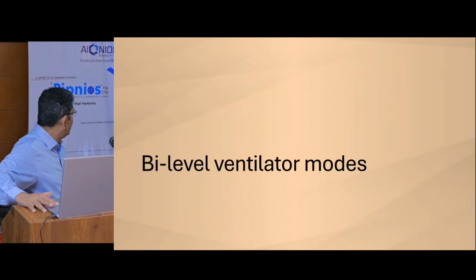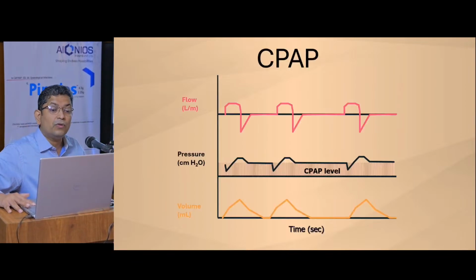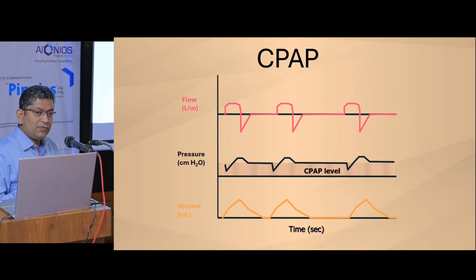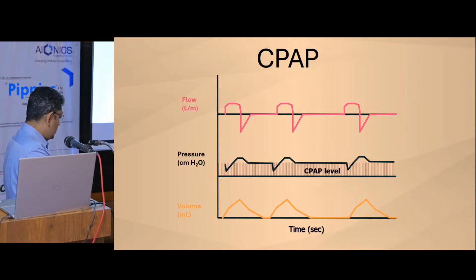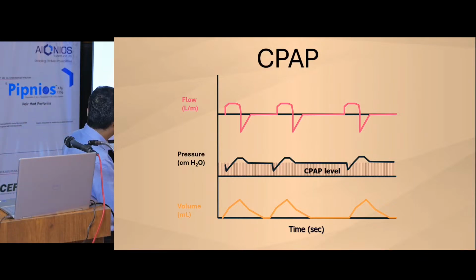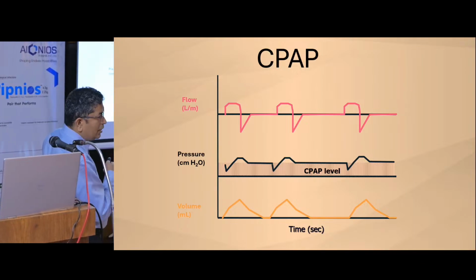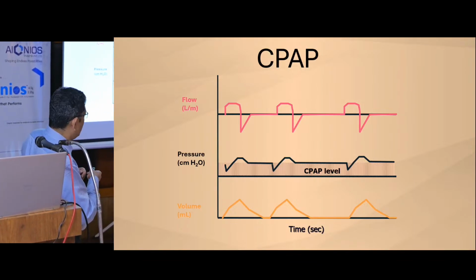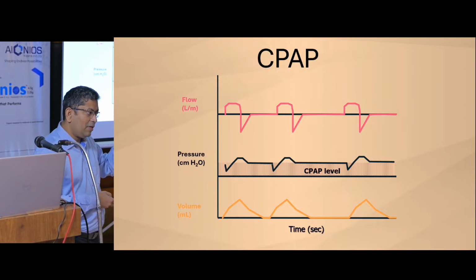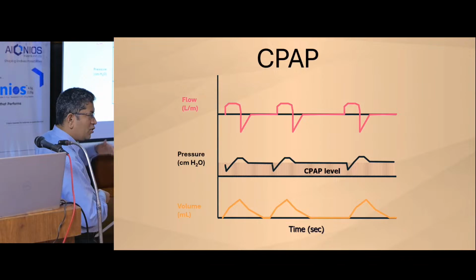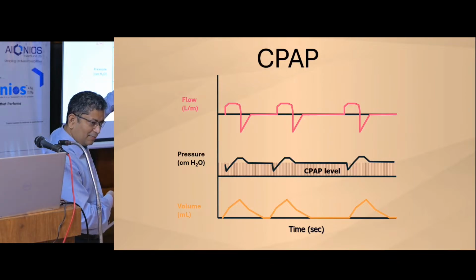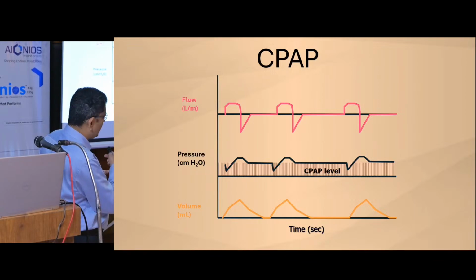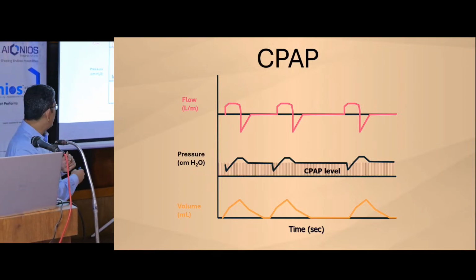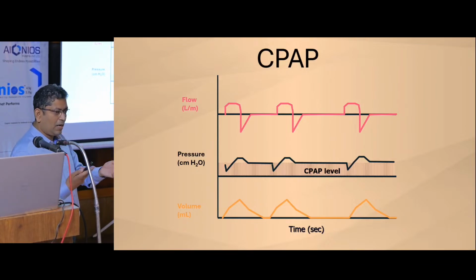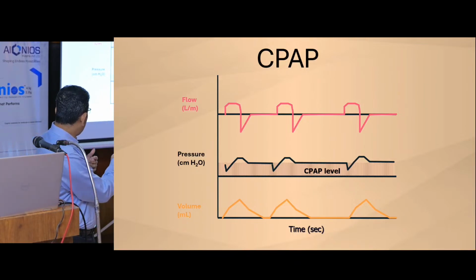And last, not the least, the bi-level ventilator mode. For that, you need to know CPAP. I think everybody knows CPAP. It just gives a pressure support, and the patient can breathe on their own on top of it. So that's the pressure level, and the patient breathes. On inspiration, the flow goes up and the pressure actually comes down here. Normally, in every ventilator, when the patient inspires, the pressure goes up. That's positive pressure. In CPAP, the pressure goes down, and when the patient breathes out, the pressure goes up. That's what happens normally in our body.